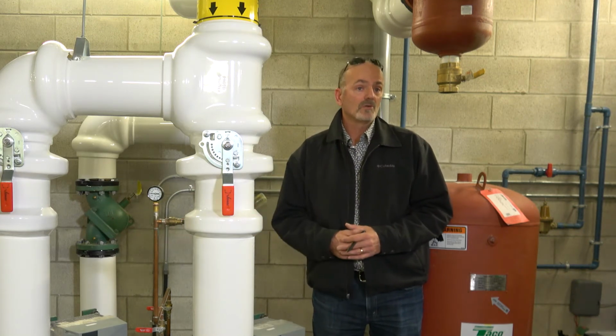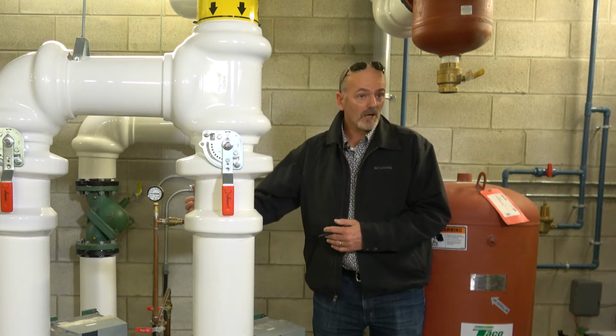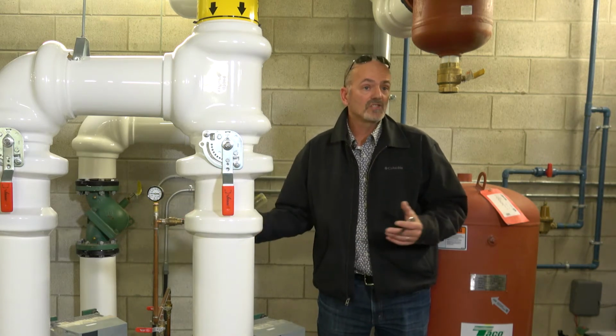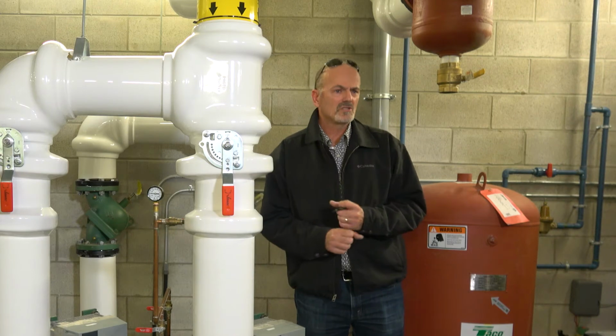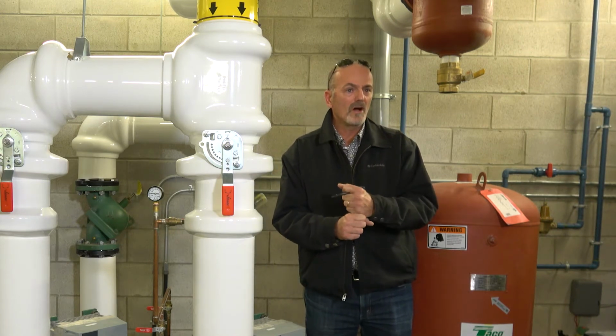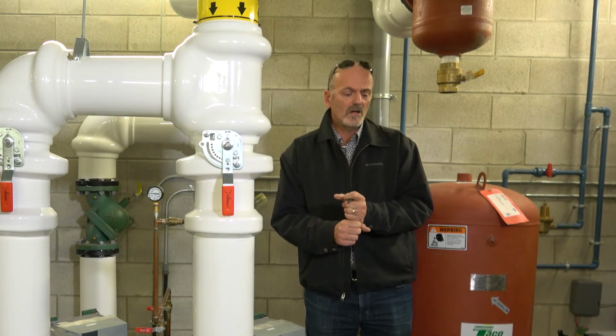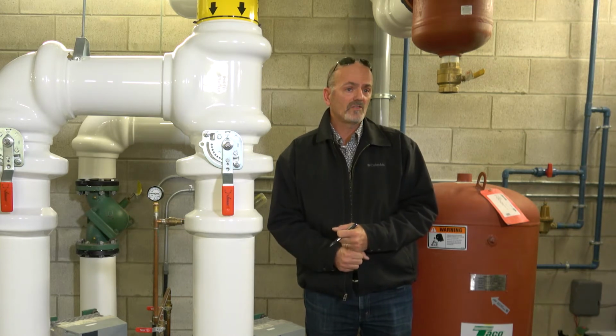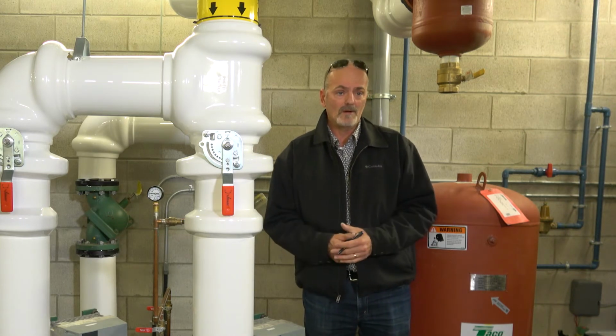Next time you do happen to turn it on, say if we're not doing it automatically, in a year or 6 months, that seal could be stuck to the point where when that motor turns on, it can actually cause that seal to crack. One of the surfaces can get pulled apart. Now you have a leak, right?